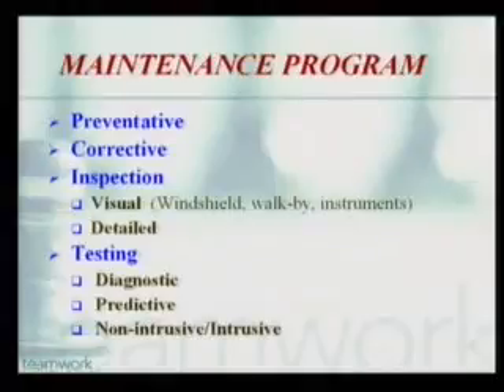We have visual inspection, where we call it windshield on power poles, where our inspector can actually just drive by, look through the windshield, or they can do walk by, or through instruments. That's gauges on the equipment. There's detailed inspection, which comprises cleaning, dusting, checking for loose connections, and so forth. And then when we come to testing, there's diagnostic testing, where we're actually using instruments to verify how the equipment is responding to a specified standard. We may go into some timing requirements, especially with circuit breakers, where timing is down to the milliseconds.